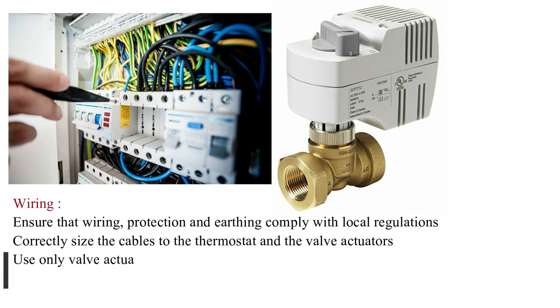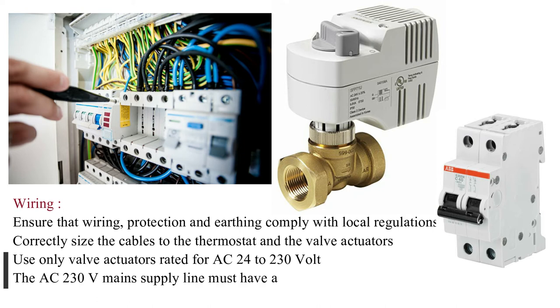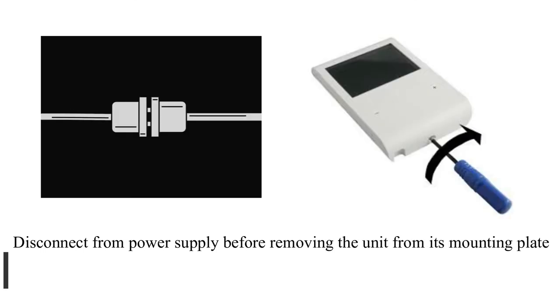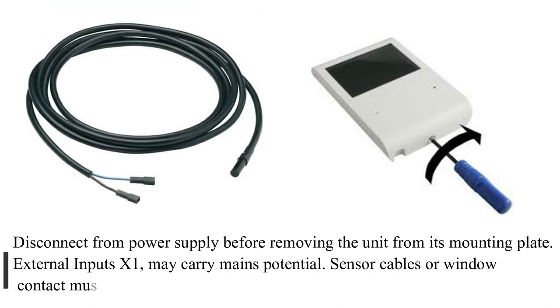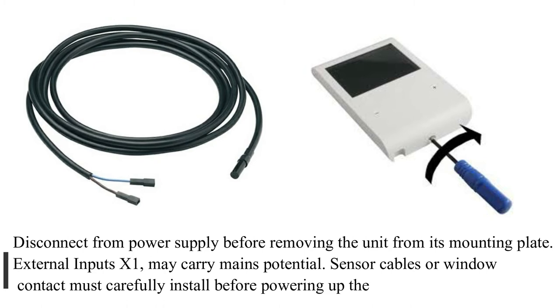Wiring: Ensure that wiring, protection and earthing comply with local regulations. Correctly size the cables to the thermostat and the valve actuators. Use only valve actuators rated for AC 24 to 230 volt. The AC 230V main supply line must have a circuit breaker with a rated current of no more than 10 amps. Disconnect from power supply before removing the unit from its mounting plate. External inputs may carry mains potential. Sensor cables or window contact must be carefully installed before powering up the thermostat.